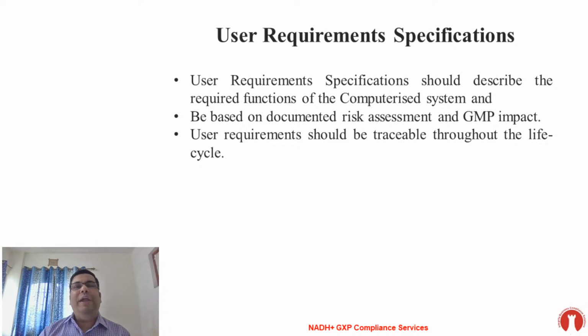You cannot say, okay, the instrument has become old, so its functionality is reduced, then it is of no use. When you develop the URS, what is its performance today? Your expectations are today with the software or computer system. Same expectation should be there up to the end of the shelf life. If you are not meeting that expectation, then you have to reduce its shelf life.